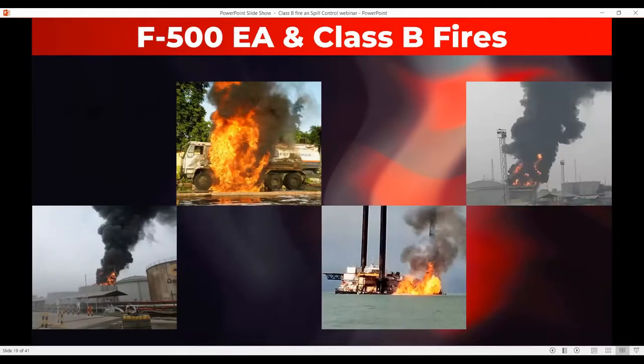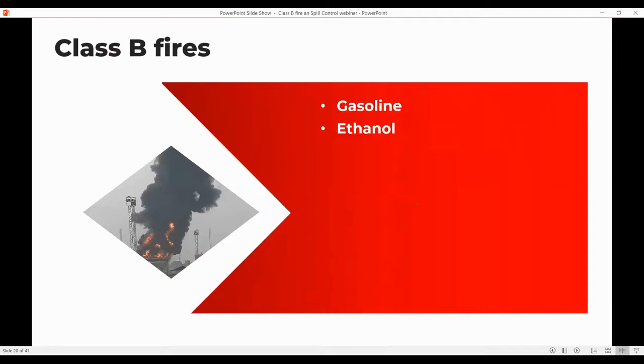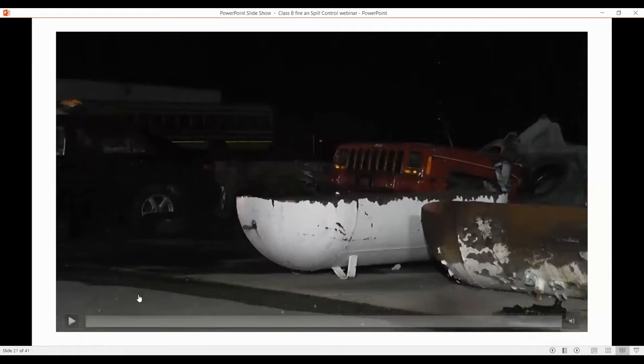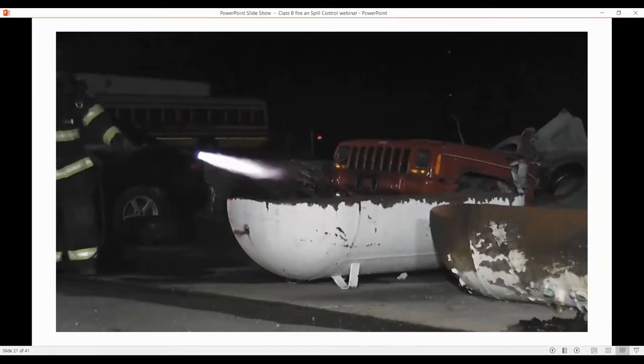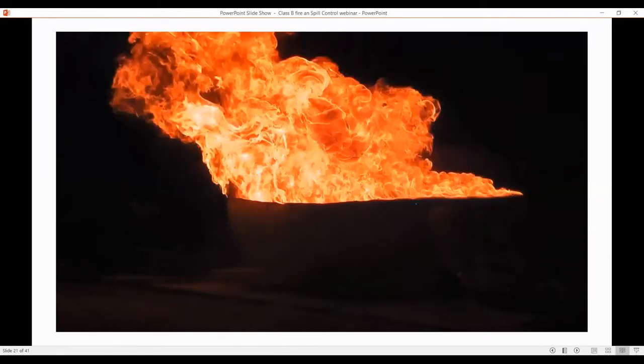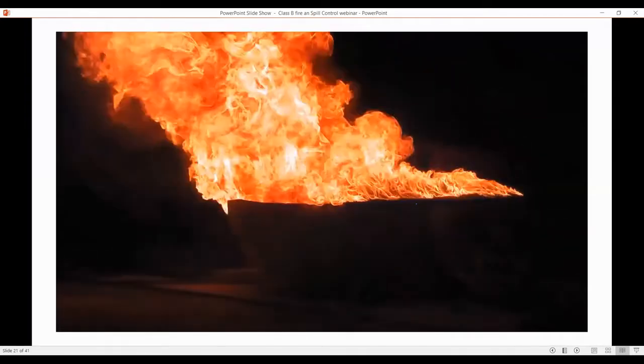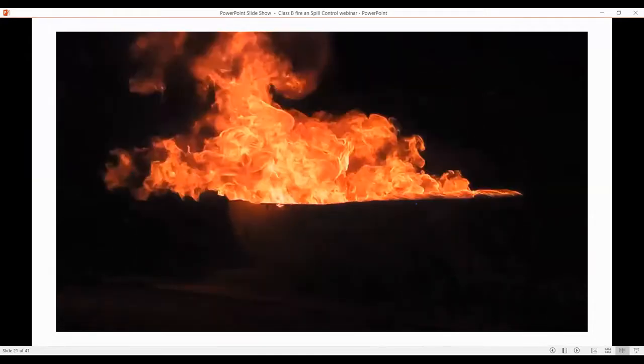Now let's look at F500 and some different Class B fires. When we're talking about Class B fuels, we're talking about gasolines, ethanols, diesel fuel, oils — both polar and non-polar. This first video is E85 gasoline floating on a pan — a burn done about four to six months ago. We're going to give it about a 40-second pre-burn to get that steel tank nice and hot. We're using a 125 gallon-per-minute hand line at a 3% solution — the most you ever have to go with F500. So even though this is a polar solvent, we're still only going to fight this fire at 3%.